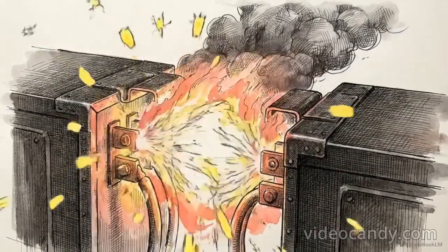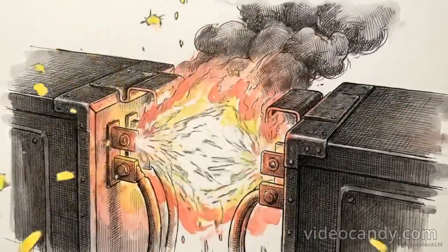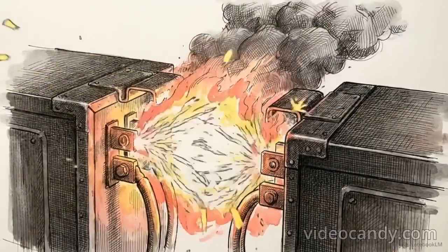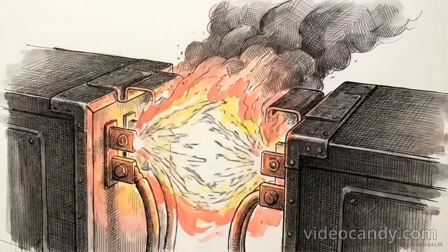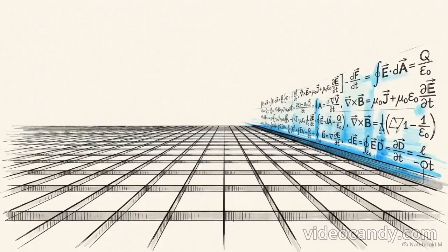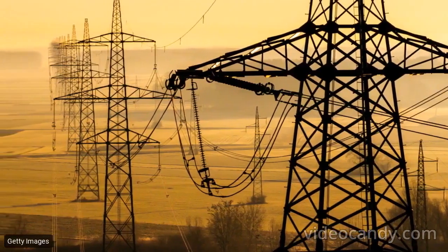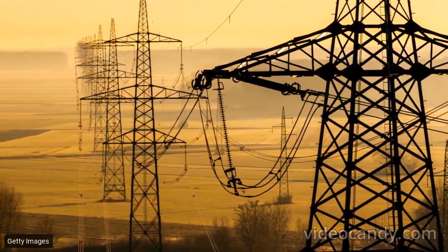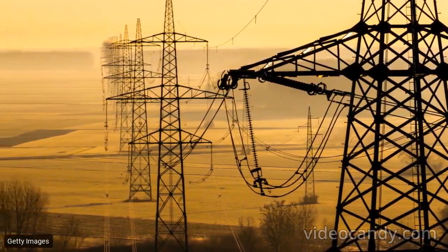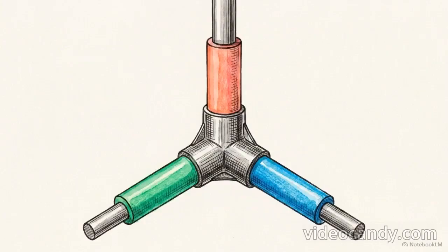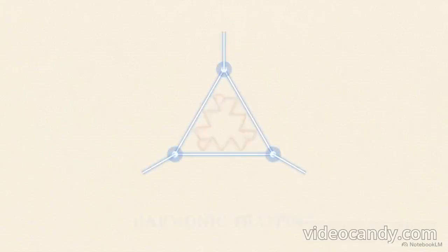This is why it is mathematically impossible to wire a Y-delta bank in parallel with a delta-delta bank. Even if their voltages match perfectly, that inherent 30-degree phase shift puts the waveforms permanently out of alignment. Ignoring this displacement causes a massive voltage difference. The result is an instantaneous catastrophic short-circuit current that will absolutely destroy the hardware. Phase geometry acts as an absolute physical boundary for grid expansion. Mathematical misalignment cannot be bypassed simply by installing more copper and iron.